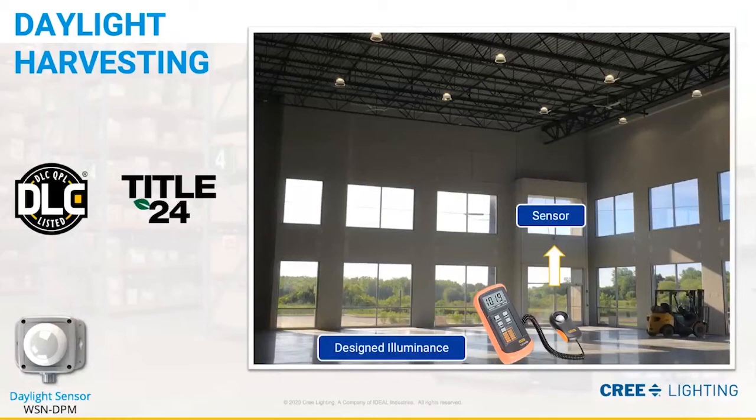We are listed on the DLC qualified product list for indoor and outdoor, and we've been working with DLC for years. Daylight harvesting is becoming more common as a code requirement in different parts of the US and Canada. A lot of people may have experience with it in an office environment, and those are closed loop systems where you have a sensor pointed down at the surface measuring the illuminance levels. The issue with that in high bays is you can't reliably measure the illuminance at 40 feet where the lights are installed.